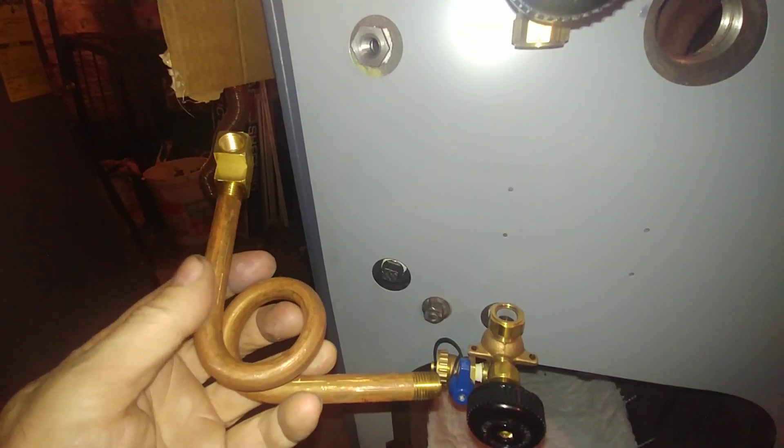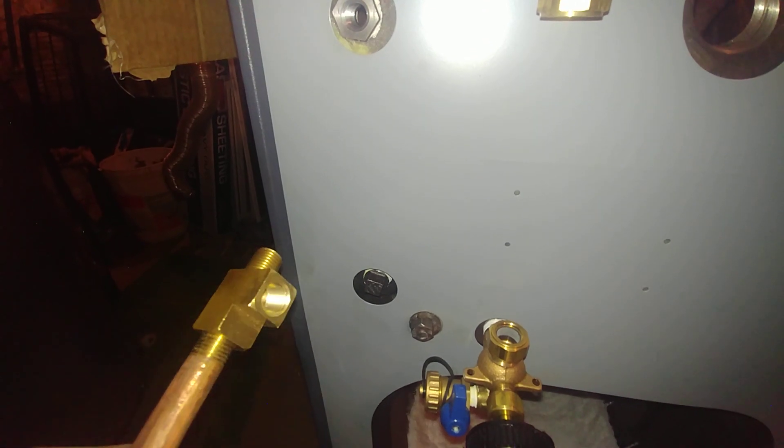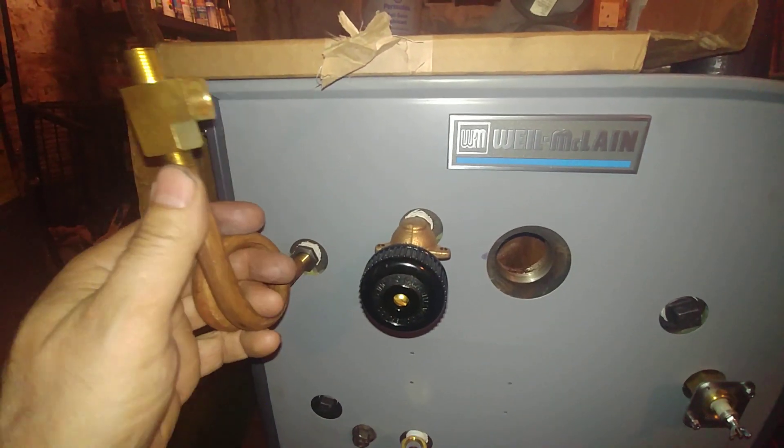This is where the pressure control and gauge gets mounted. We're going to be using a 240 pigtail with a quarter-inch male T where we put the gauge here and the pressure control there, and it's going to go on like that.